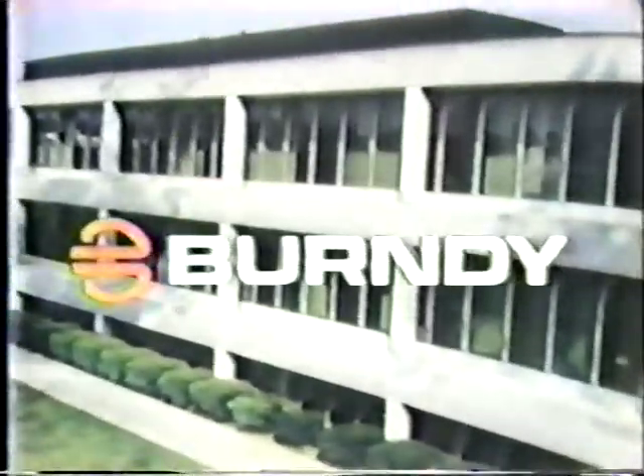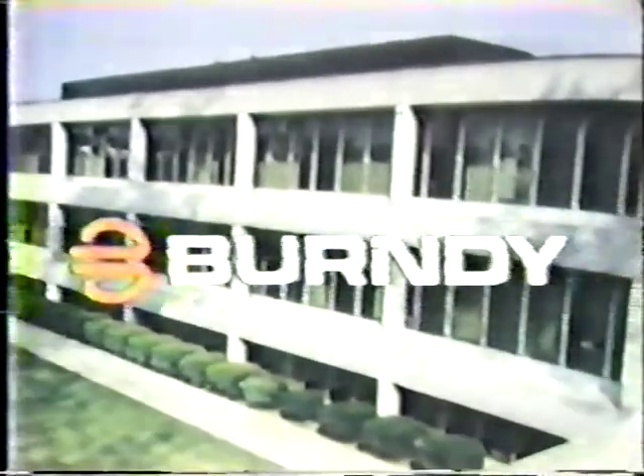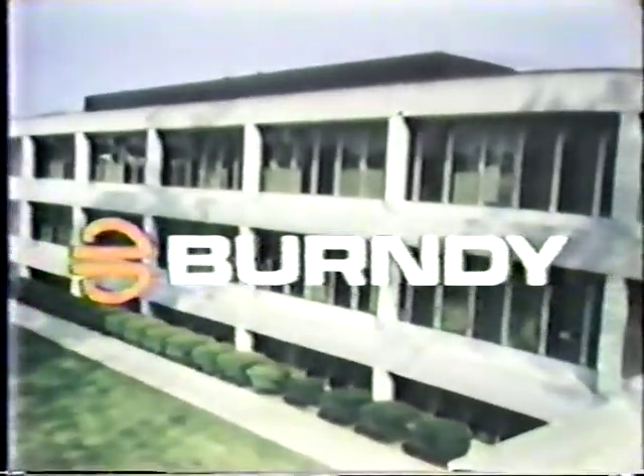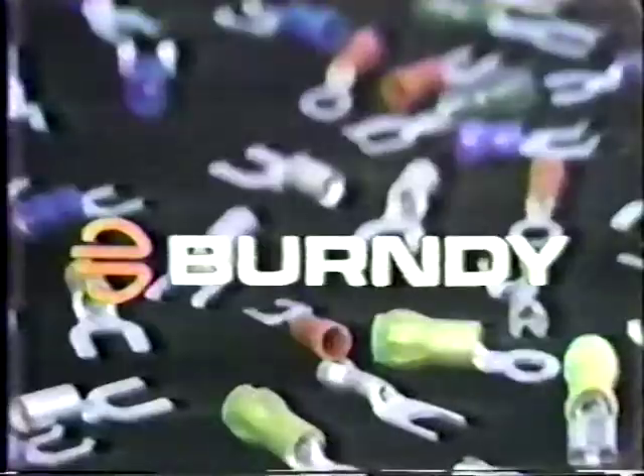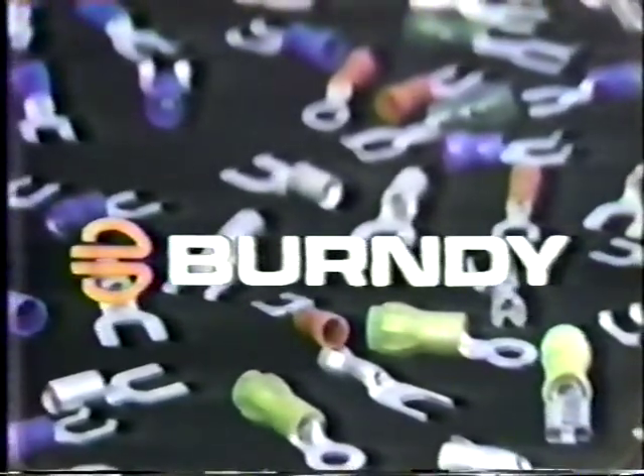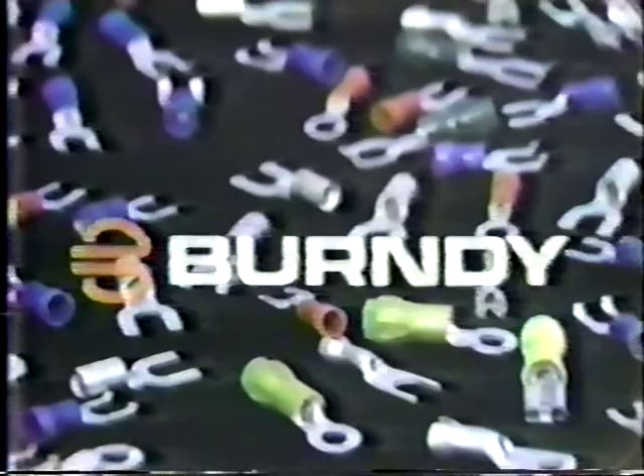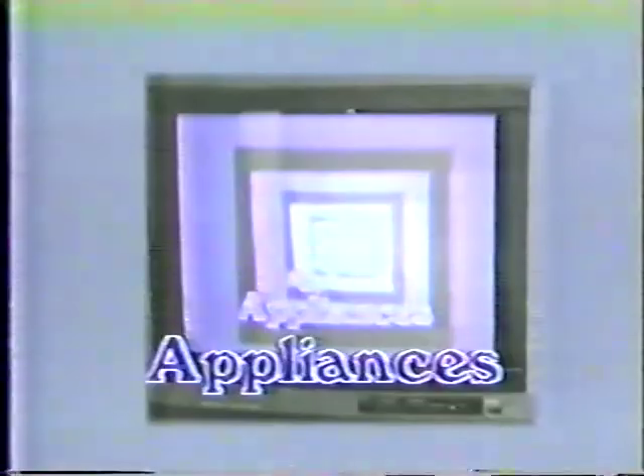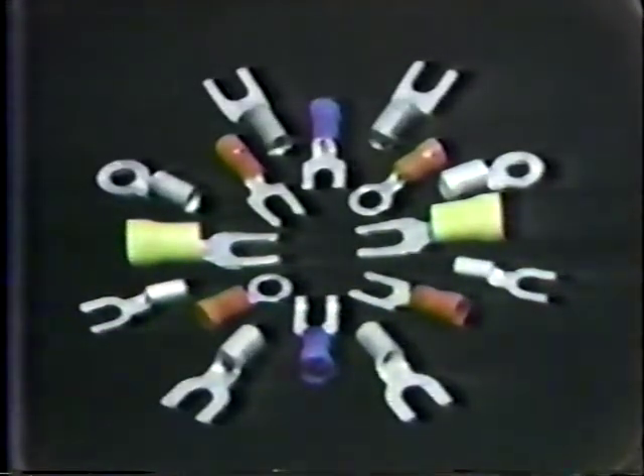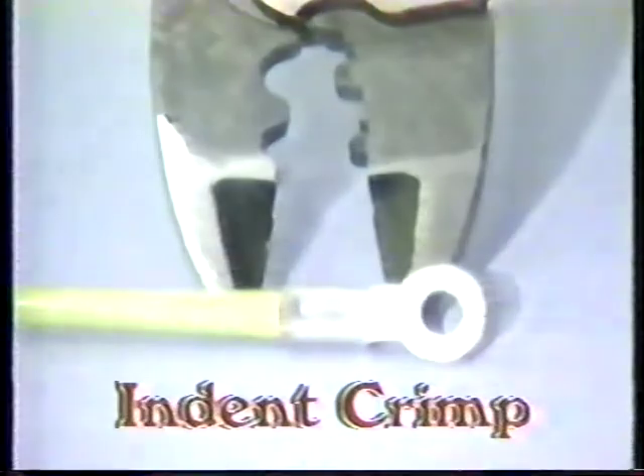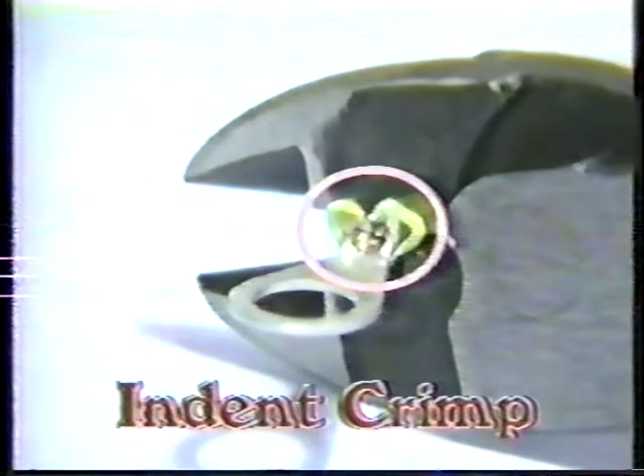By following Burndy's tradition of recognizing the physical and financial needs of the electrical contractor, we've applied our engineering expertise to small compression terminals and splices. The results are cost-effective innovations geared to the control circuits used in machinery, automotive, appliances, and computers. Everyday applications require both insulated and uninsulated connectors. An indent crimp is ideal for uninsulated or bare connectors. However, the indent may pierce and destroy the jacket of insulated terminals and splices.